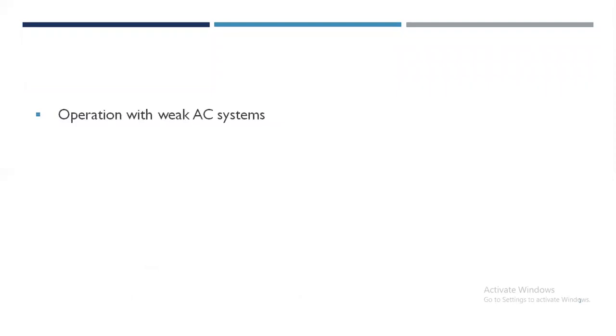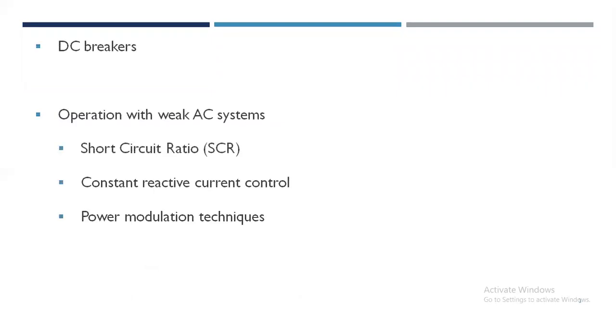The next concern is DC breakers. With the development and testing of prototype DC breakers, it is possible to go in for tapping an existing DC link or the development of new MTDC systems. Parallel rather than series operation of converters is likely as it allows certain flexibility in the planned growth of the system. The DC breaker ratings are not likely to exceed the full load ratings as the control intervention is expected to limit the fault current.